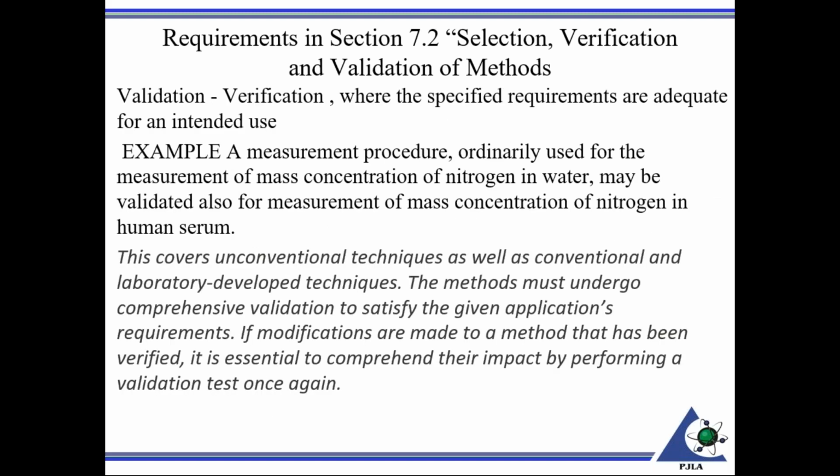Going on to the other term, validation. Validation is a verification where the specified requirements are adequate for an intended use. An example would be a measurement procedure ordinarily used for the measurement of mass concentration of nitrogen in water that may be validated also for measurement of mass concentration of nitrogen in human serum.